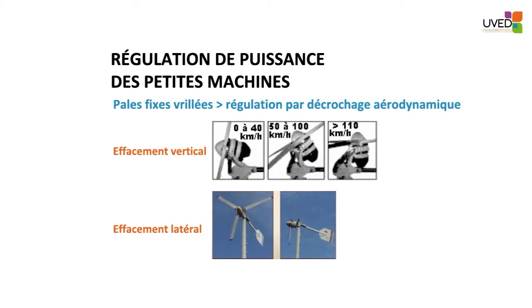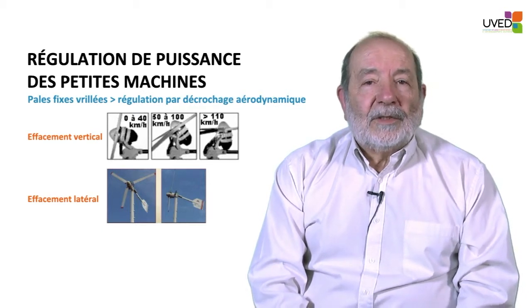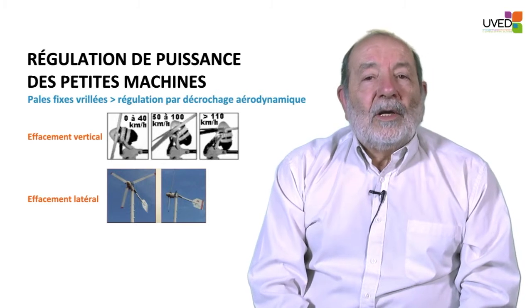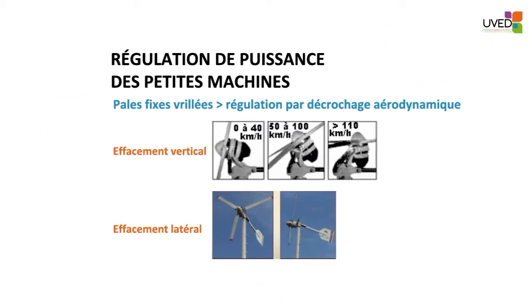Small windmills with small blades do not have this kind of system. They are regulated by aerodynamic stalling. The blade is designed so that above a certain wind velocity, lift will decrease and this will reduce the revolution speed. If the wind is very strong, the small windmill will pitch vertically or laterally to decrease contact with the wind.